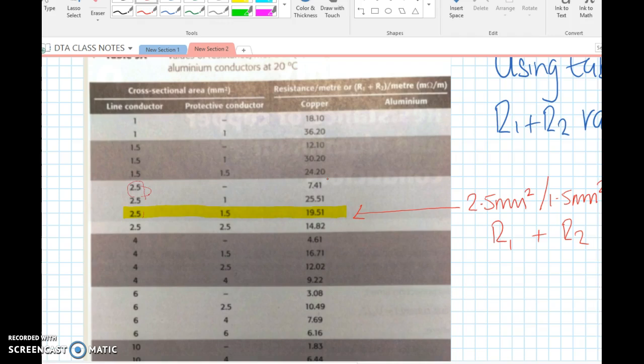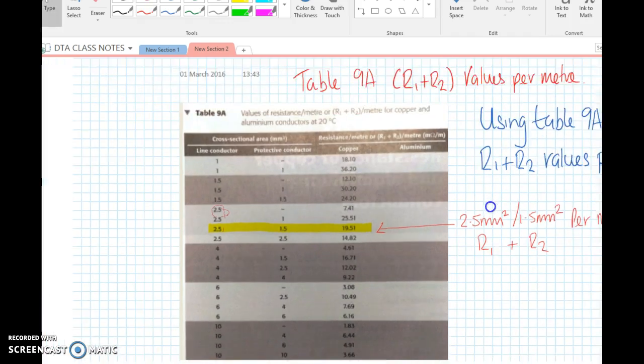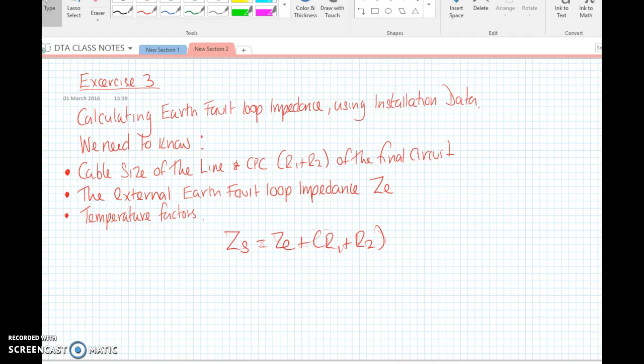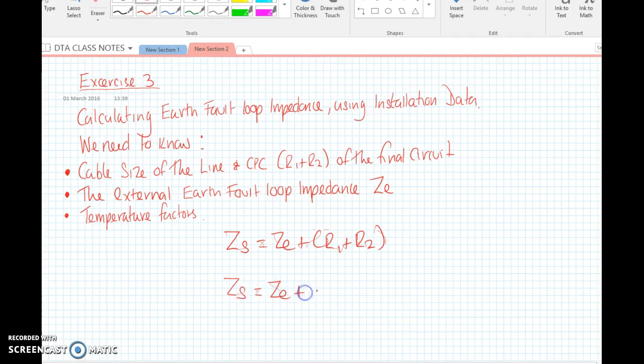For a 2.5 millimeter cable on its own, it has a resistance per meter of 7.41 milliohms at 20 degrees C. But what happens if our installation isn't running at 20 degrees C, or our circuits are loaded up? Normally the conductors can operate up to 70 degrees C, so we can add some temperature factors.